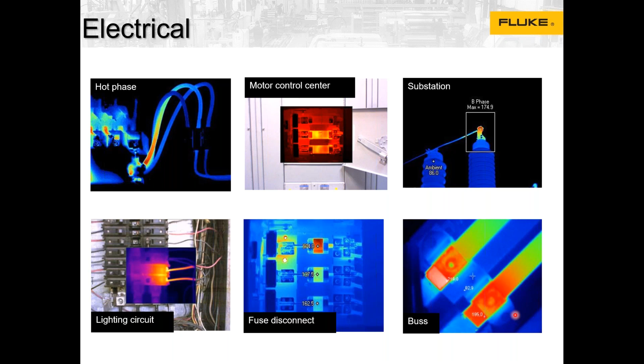The bottom middle one is showing three different colors, and we have also added some temperature data that indicate three very different temperatures. You can see 274, 107, and 162. Probably due to a poor connection, for example, due to the heat at the connection point, and then the temperature becomes more normalized the further you get from the connection. We have also here a picture coming from buses, so we can see that there is one which is hotter than the others, and we have even the temperature data. So very easy also to interpret the pictures.